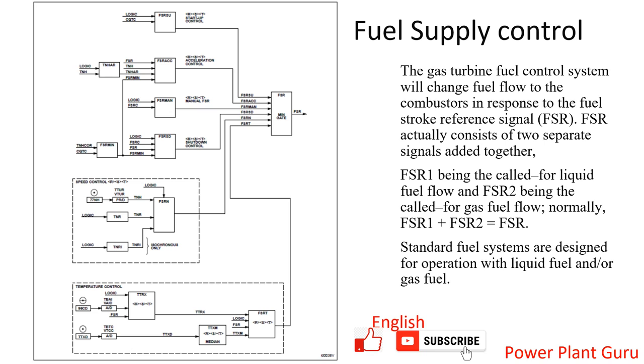Fuel stroke reference, normally called FSR, is a very important parameter in gas turbine terminology. FSR is basically a fuel supply rate and this FSR may depend on a lot of various parameters such as inlet air temperature control, machine loading, type of fuel, etc.